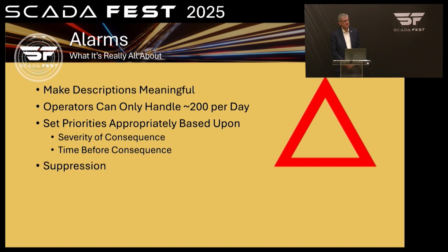Take advantage of alarm suppression. This is an important feature for looking at alarms, because you get these alarms when someone goes in and turns the power off on a panel, and all of a sudden you get 20 alarms because the power's off. That's not a useful piece of information for the operator. The operator has to recognize, these are all coming, I bet you somebody turned the power off. You don't have to put that burden on the operator to figure that out. It would be much better to say there's a power off problem. And the way you handle the extra nuisance alarms is that you put a suppression or a conditional on the alarms that are consequent.